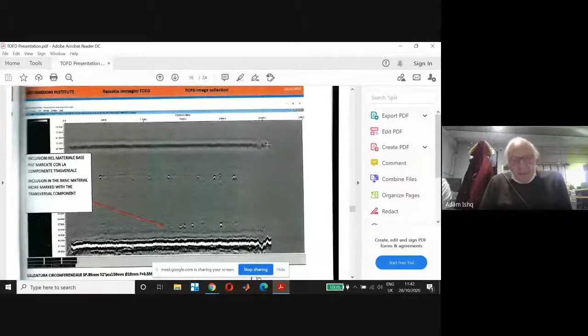Now we go to the picture. Okay, now this is a typical picture of time of flight. We call this a scan. You see, this is the thickness of the material, and these small black and white marks, you always see black and white. Black and white are small inclusions inside the material. We have a big reference. The brightness of the black and the brightness of the white are related to the amplitude of the signal. So if the signals are small, then you see only the roughness around. The surface is not flat. You see very small marks, which means a very small noise level and so on.